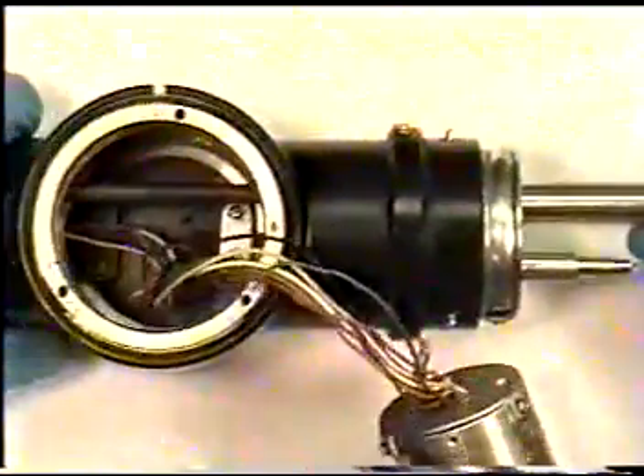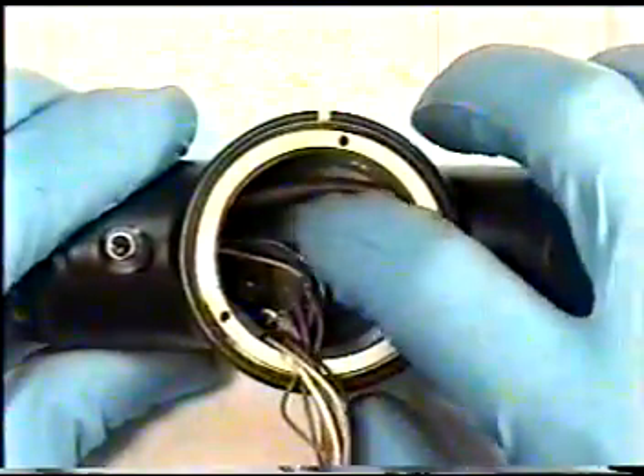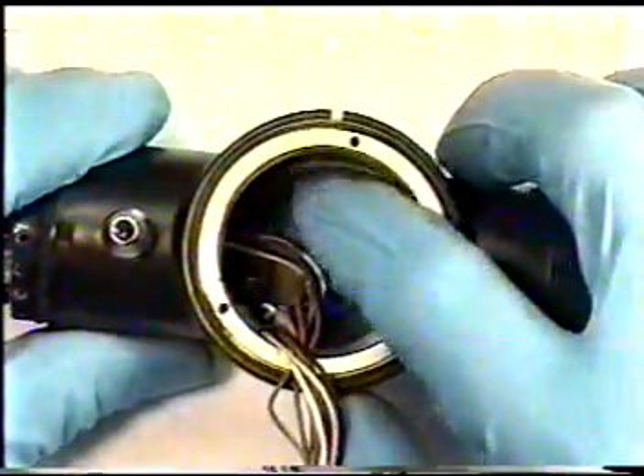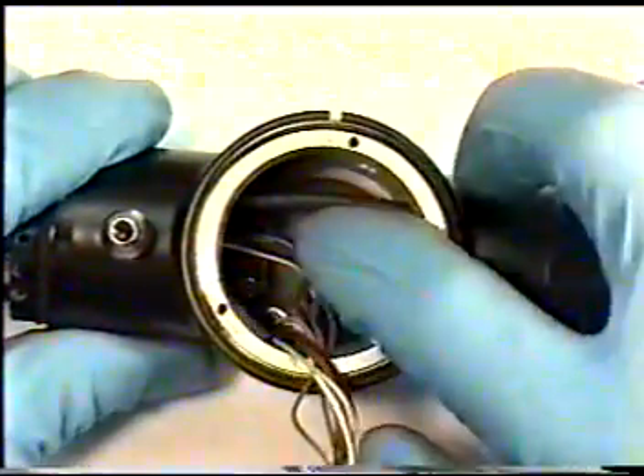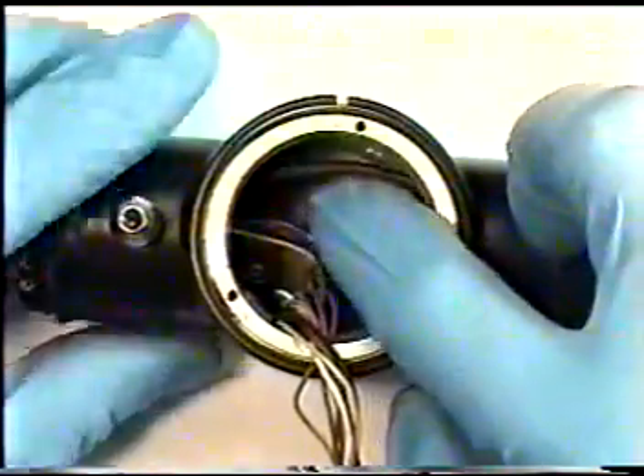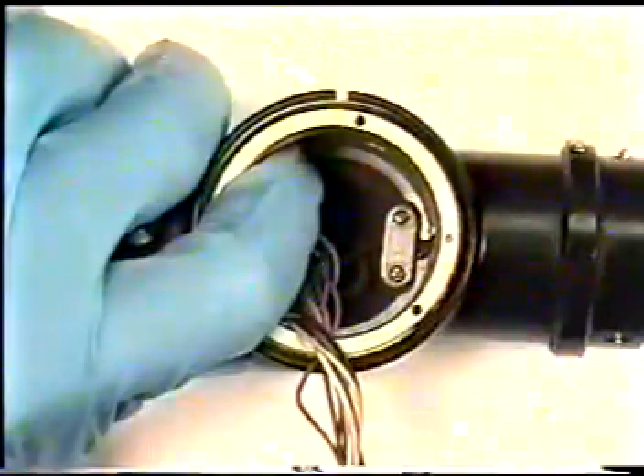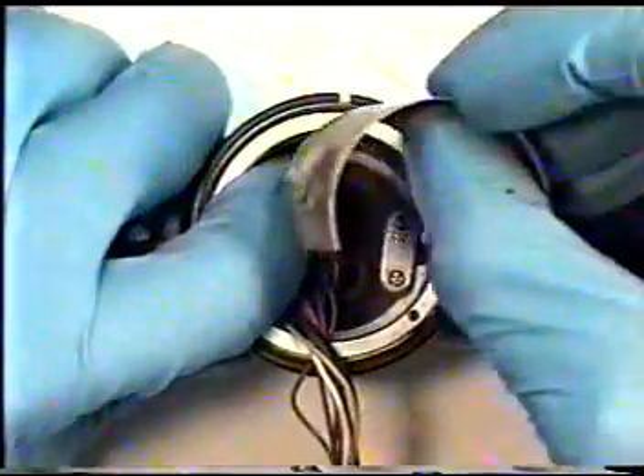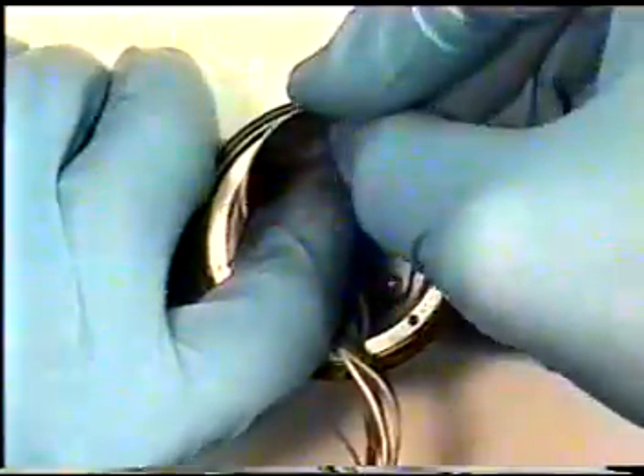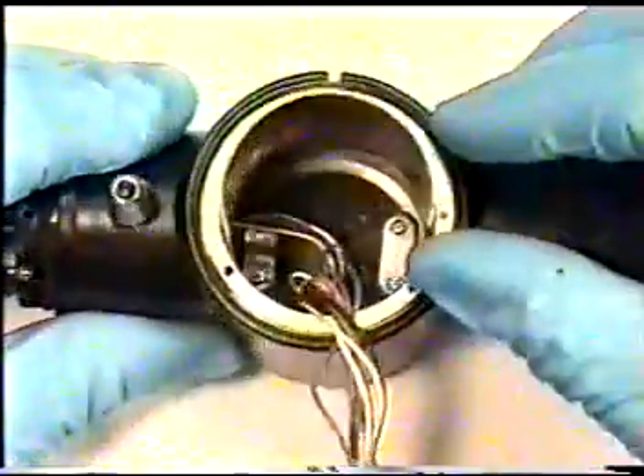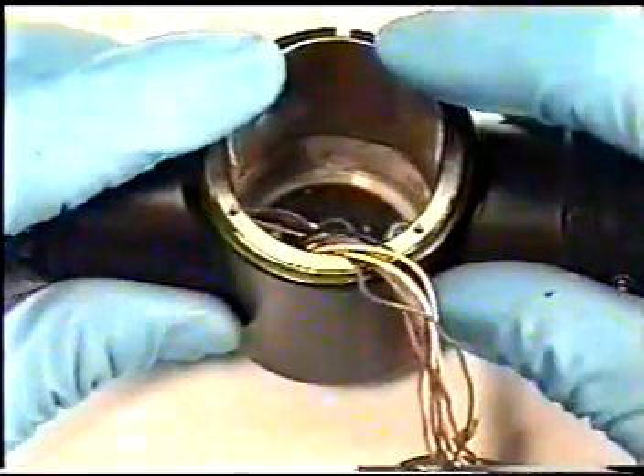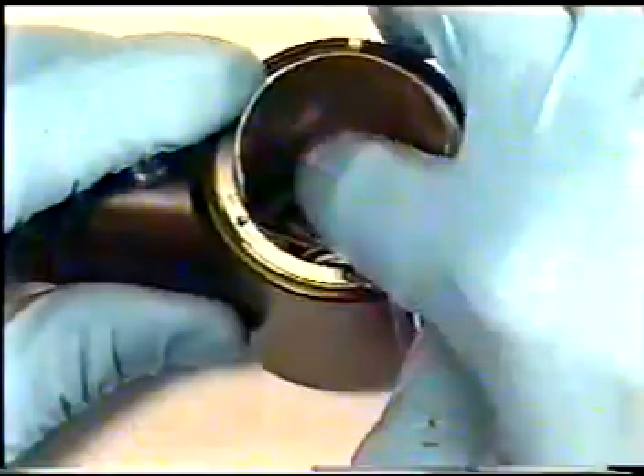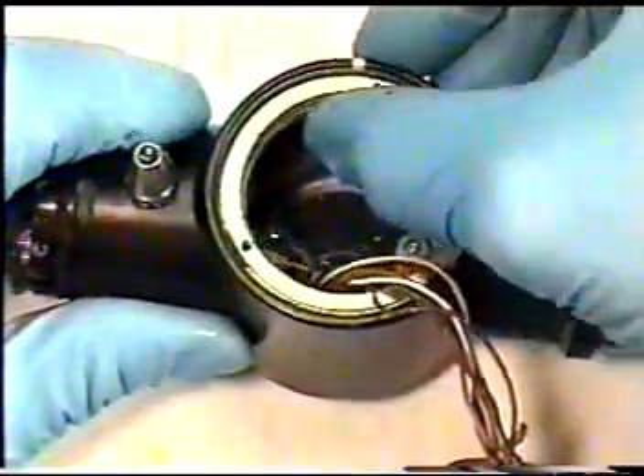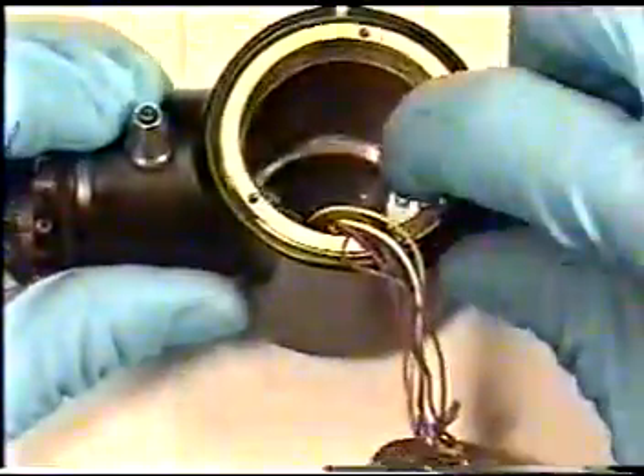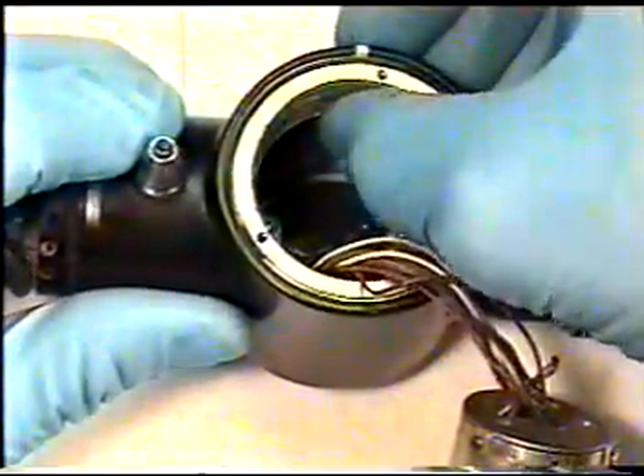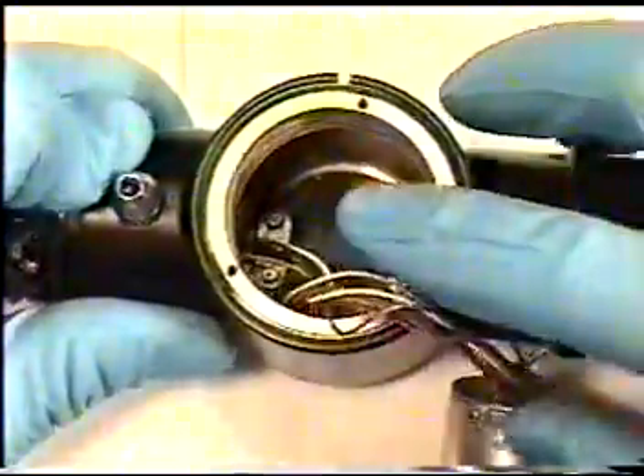With your light guide probe sealed properly, you will now need to push our new light guide bundle up against our connector wall, in this case Olympus Video Endoscope GIF 100. Push your light guide up against the wall, retrieve your copper plate, slide the plate over the light guide bundle, and be extremely careful not to pinch or crush your light guide bundle as you're pushing down this plate, otherwise you will cause severe damage to your new light guide bundle. The copper plate fits in only one fashion, so be careful when pushing down as not to crush or pinch your new light guide bundle.